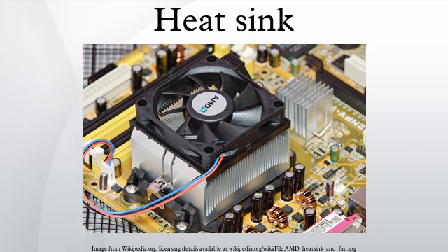Thicker tapes tend to provide better wettability with uneven component surfaces. Wettability is the percentage area of contact of a tape on a component. Thicker tapes, however, have a higher thermal resistance than thinner tapes. From a design standpoint, it is best to strike a balance by selecting a tape thickness that provides maximum wettability with minimum thermal resistance.